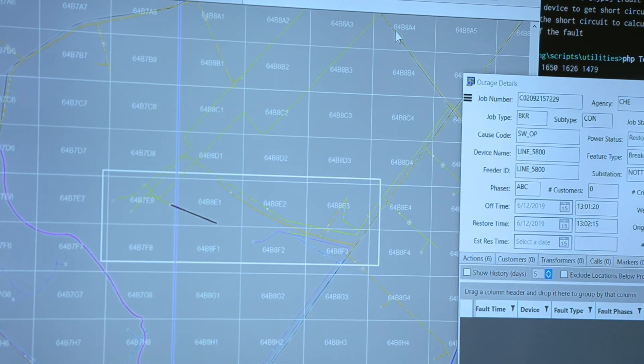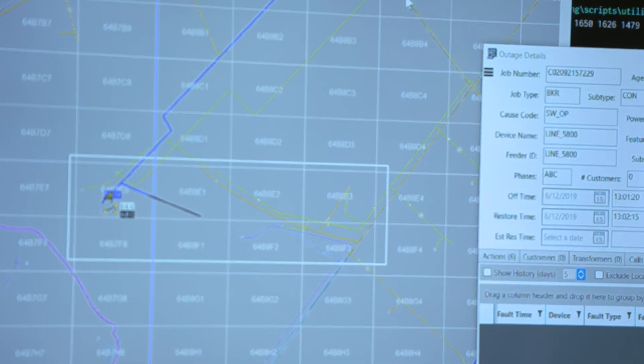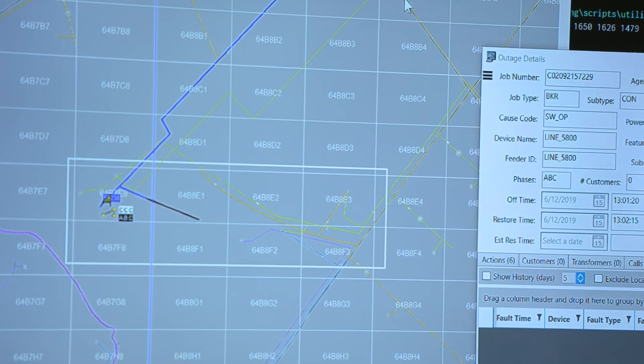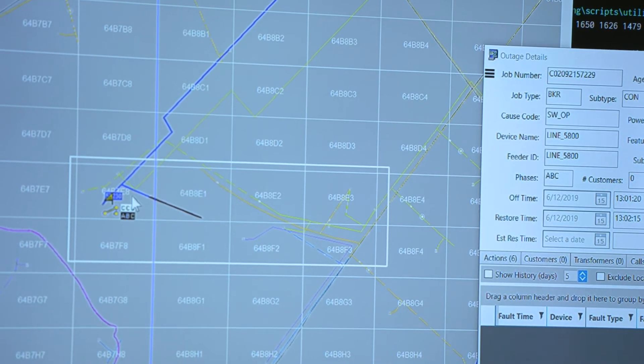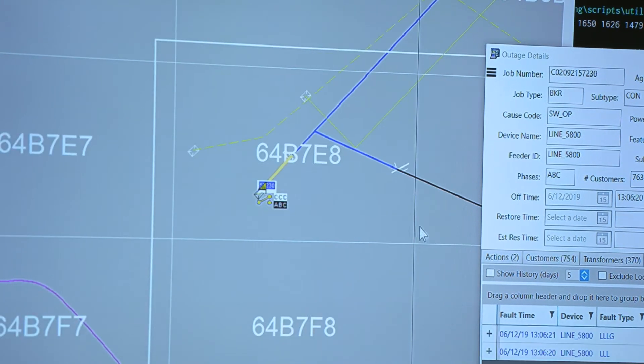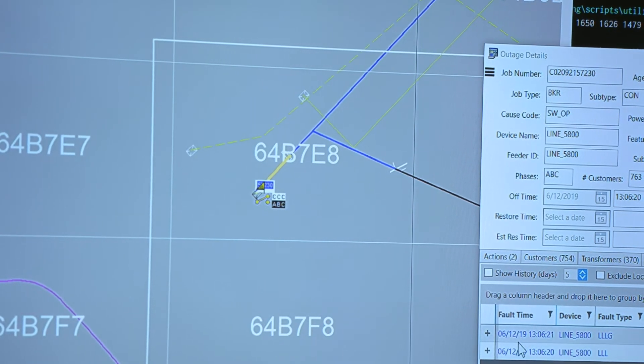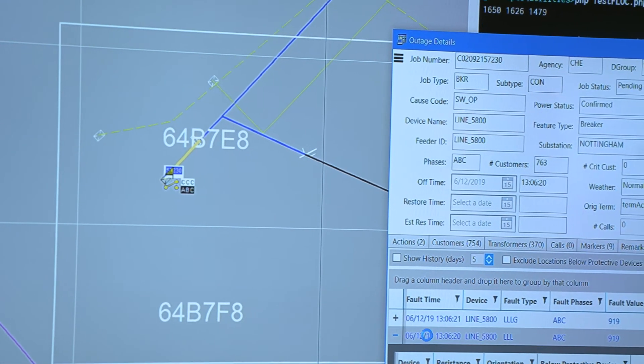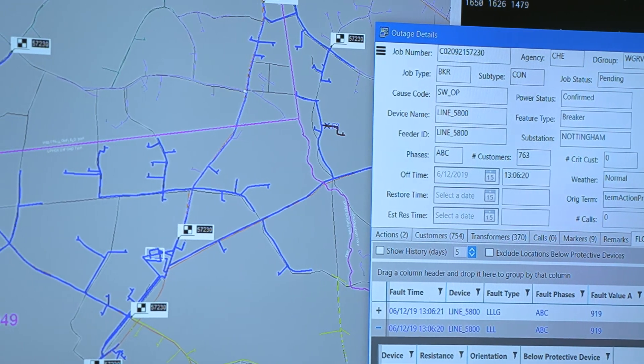Chad's simulation is bringing in real-time data that the power company already has from their SCADA system and performing all the analytics to pinpoint those possible fault locations. So right now we've produced an outage right here — a breaker outage. If we have a look at the breaker outage, it has produced two fault analyses, and these have highlighted a chunk of the network where it thinks the fault most likely is.